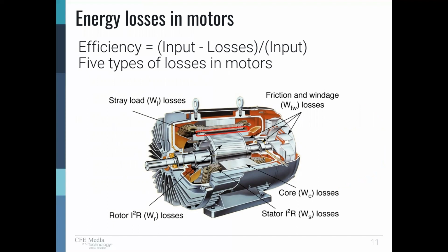Before I go into those, though, look at the formula at the top. Efficiency is input minus losses divided by input. Input minus losses turns out to be our output. So in the simplest of terms, energy efficiency is output divided by input. When we try to measure the load on a motor, the losses are a very small part. If we measure output over input, a big number over a big number tends to be not very accurate. So we'll discuss what these losses are to get a better appreciation of how small they are and what happens with them.